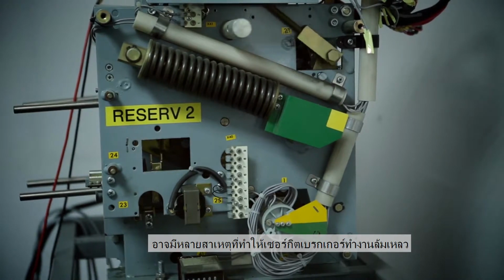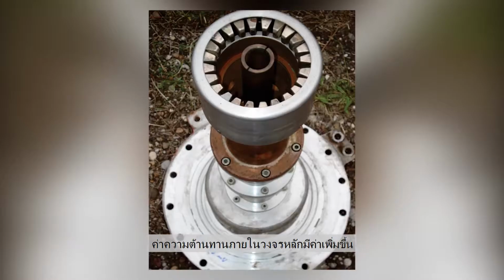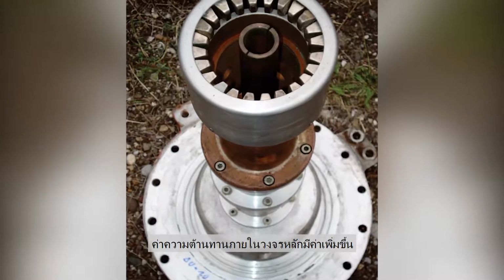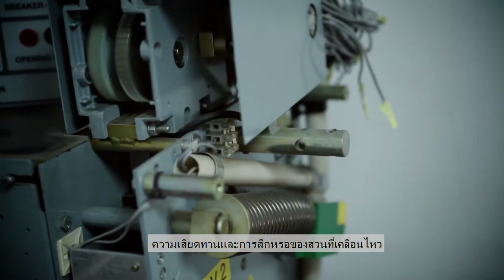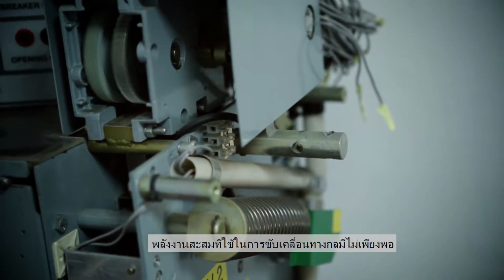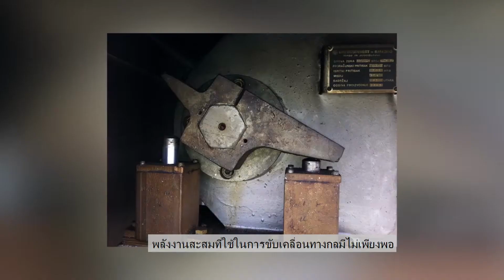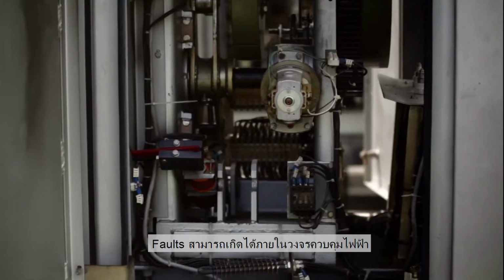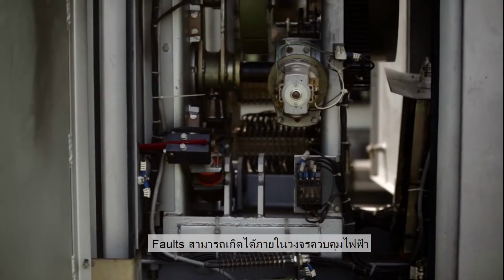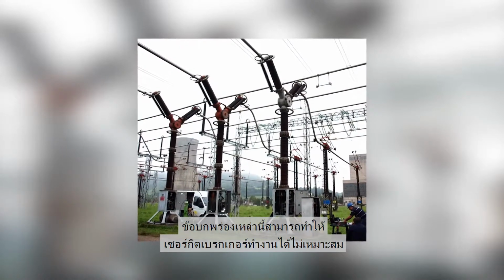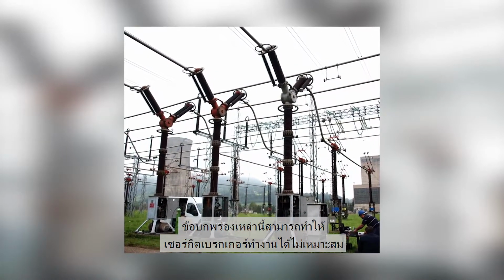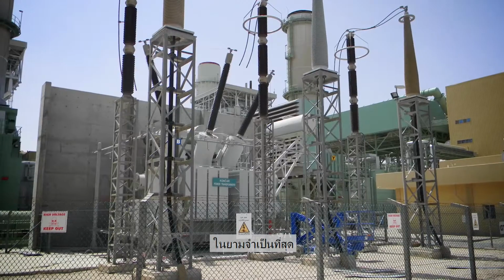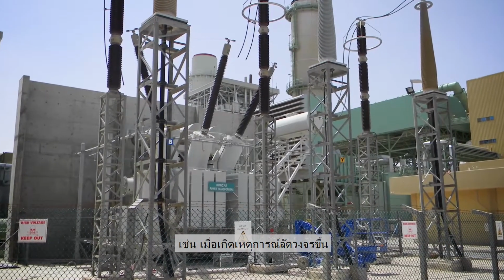There can be various causes of circuit breaker failure: increased resistance of a main circuit, friction and wear of moving parts, insufficient storage of driving energy in the operating mechanism, improper damping devices. Faults can also occur in electrical control circuits. All these defects can cause a circuit breaker not to operate properly when it is needed the most, such as a short circuit fault.